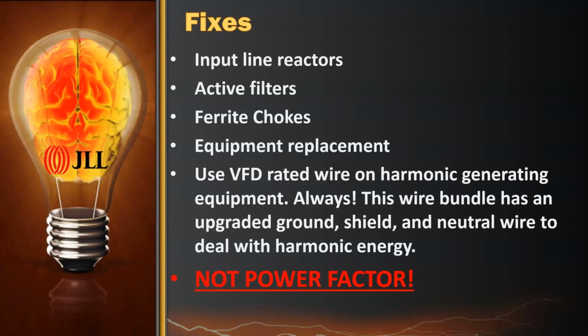And from the utility's point of view, the utility would look at that and say, well, this isn't bad. I get more money, right? But they might get really nervous or anxious if you were causing so much trouble in your site that your neighbor is having a problem with harmonics. That happens a lot in residential applications, because you might have 50 houses on one transformer.